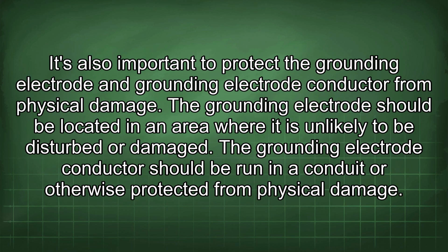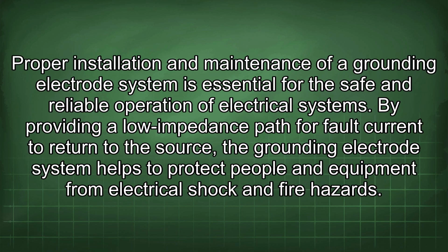It's also important to protect the grounding electrode and grounding electrode conductor from physical damage. The grounding electrode should be located in an area where it is unlikely to be disturbed or damaged. The grounding electrode conductor should be run in a conduit or otherwise protected from physical damage. Proper installation and maintenance of a grounding electrode system is essential for the safe and reliable operation of electrical systems.